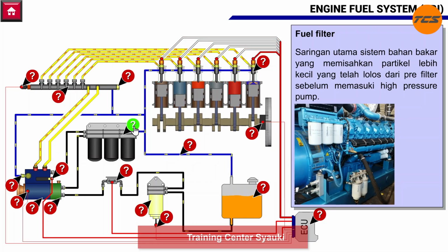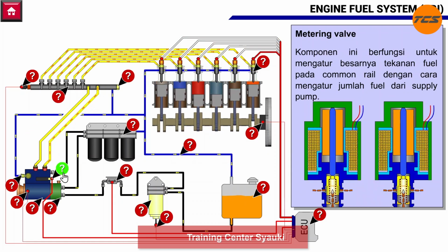This filter is the primary filtration component in the fuel system. It removes fine particles that have passed through the pre-filter in the fuel water separator. Clean fuel is critical to protect high pressure components, especially the injector and the high pressure pump, which operate under extremely high pressure. After passing through the main fuel filter, fuel flows into the metering valve section.